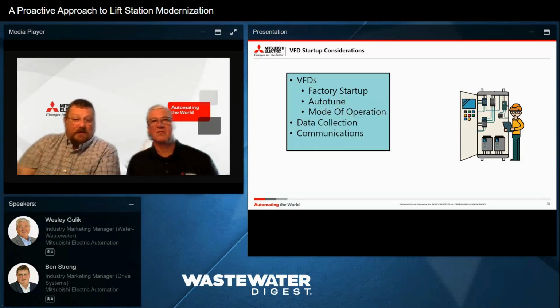And that becomes important if you want to use the advanced functions, or if you want to use the VFD as a sensor and start monitoring more information. If you truly want to know how much torque it takes for your application, not current, torque, you have to auto-tune that drive. And mode of operation is important. For a lot of lift stations, we think, well, our VFD is just a shaft turner. Let's just keep it simple. Let's keep it volts per hertz, which is fine if you understand the ramifications of that decision. But if you're operating where you need more torque, what you may consider is switching to something like a flux vector mode that requires an auto-tune.